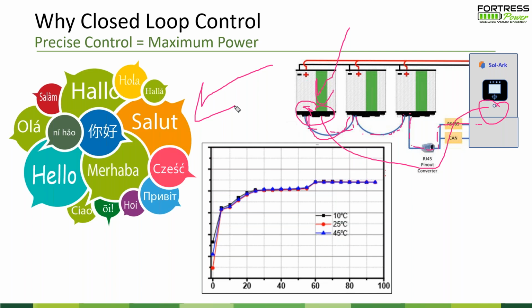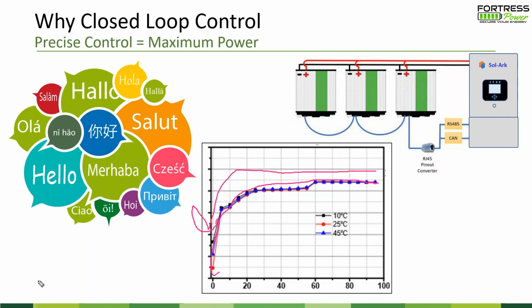These lithium ion high-tech batteries are taking over the controls in terms of telling the inverter what the percentage state of charge is. One note on percentage state of charge: it's actually pretty hard to calculate. Looking at battery voltage from 0% full to 100% full, lead acid voltage levels are more of a straight line, but with rapidly dischargeable and chargeable batteries such as lithium ion, the voltage drop curve is much more of a plateau with a big cliff at the end.